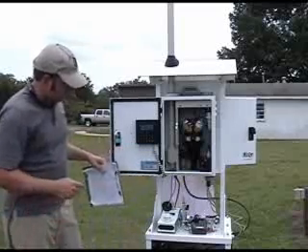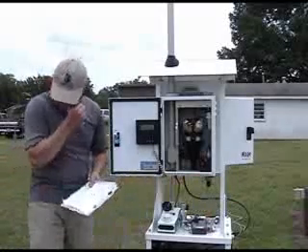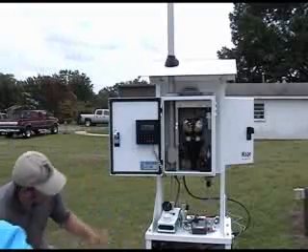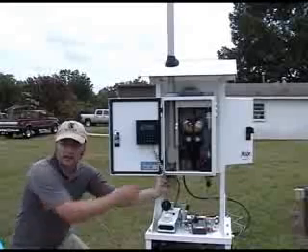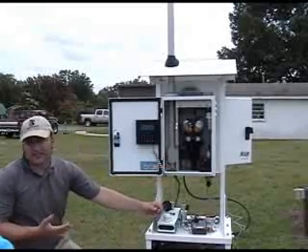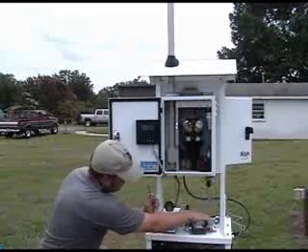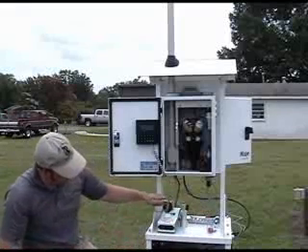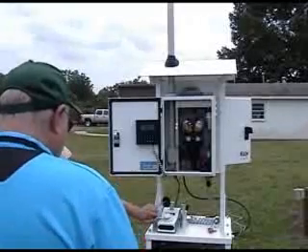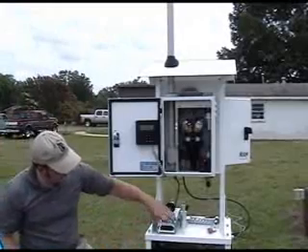Alright, so now we're ready to start some calibrations. So the temperature calibration should be done before you do your leak check, because what we're going to do is we're actually going to remove the temperature probe from the flow line. So this would effectively invalidate any previous leak check. So I have my temperature reference here that I'm going to make use of. There is a temperature sensor housed right here. It's pretty hard to make use of, especially under windy conditions.